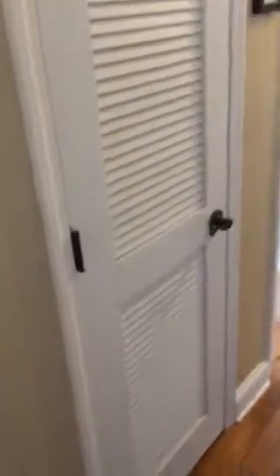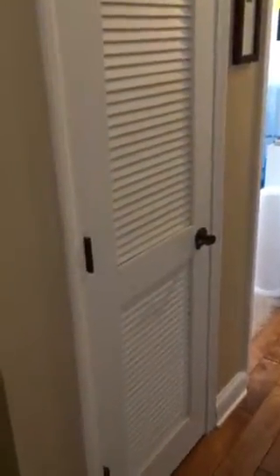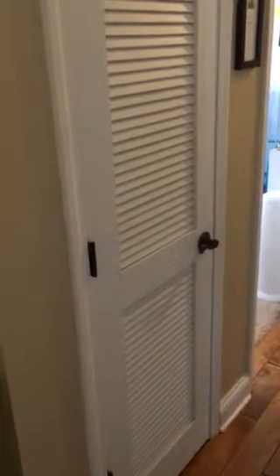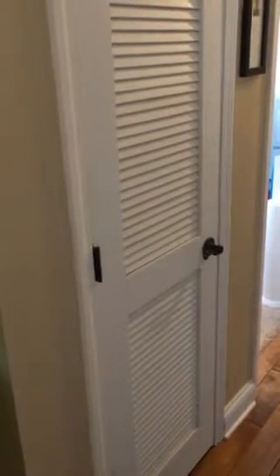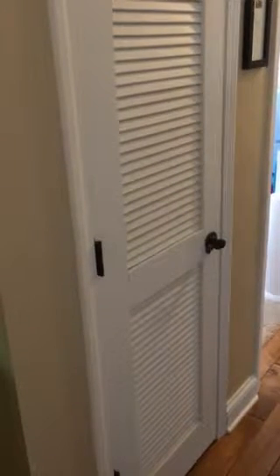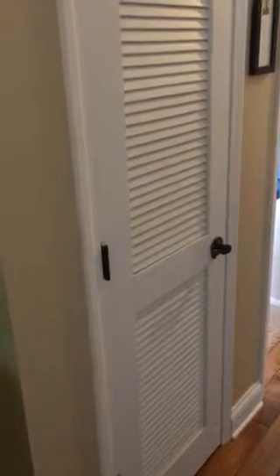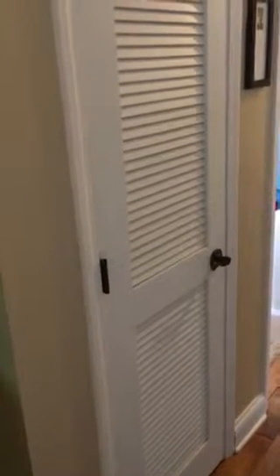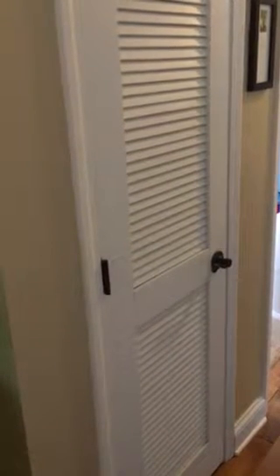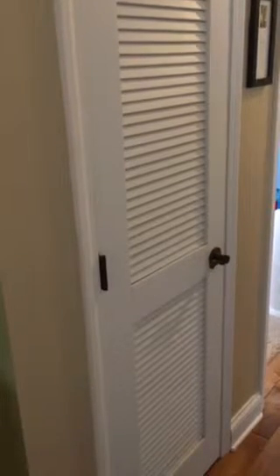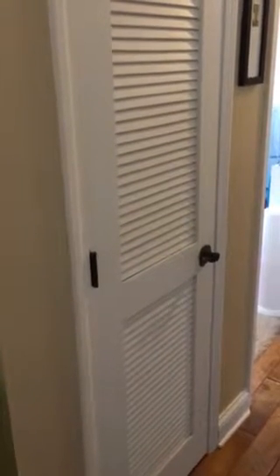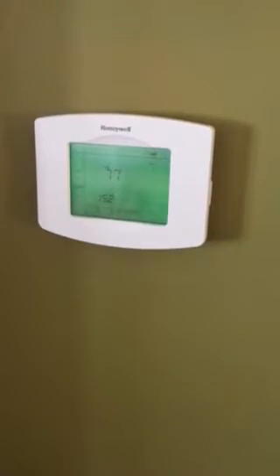In here, all you have to do is set your thermostat. I wired a separate thermostat to fan only, so my heat pump actually thinks it's running, but the only part that runs in the winter when I have my stove on is the fan portion of the heat pump. You could use your standard thermostat like I have here, and I just turn the breakers off to the heat strips in the outside unit, so it thinks it's running, but it's really not.